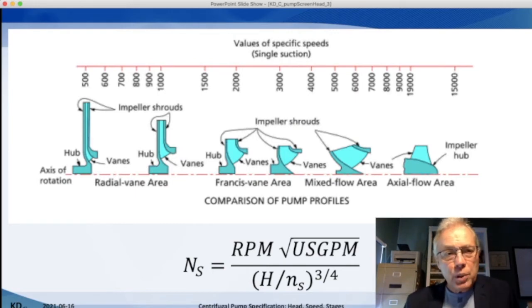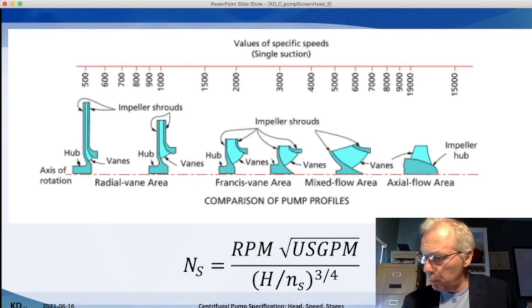A specific speed of 500 is very flat and looks like the disc brake on a car, whereas a pump with a specific speed of 10,000 or 15,000 is very axial and looks like a boat propeller.